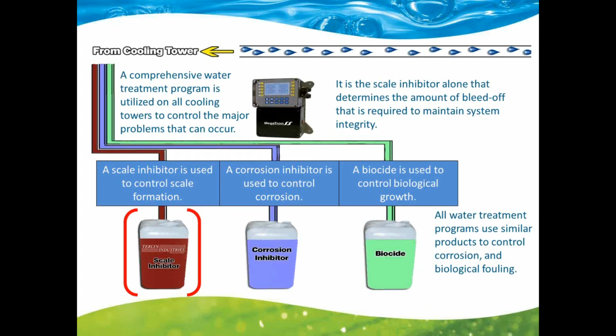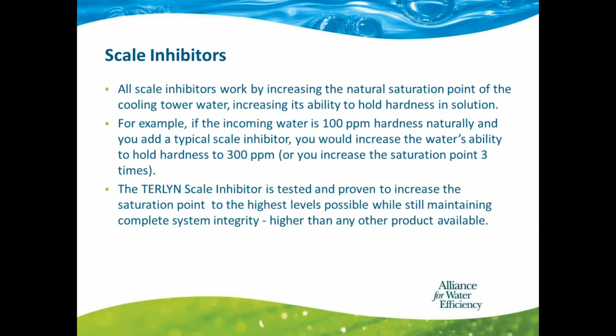It's the scale inhibitor that allows for water conservation in a cooling tower. Next slide, please. So, all scale inhibitors work by increasing the natural saturation point of cooling tower water, increasing its ability to hold hardness in solution. So, for example, if the incoming water is 100 parts per million hardness naturally, and you add a typical scale inhibitor, you would increase the water's ability to hold hardness to 300 parts per million, or you increase the saturation point 3 times. The TERLYN scaling inhibitor is tested and proven to increase the saturation point to the highest levels possible while still maintaining complete system integrity, higher than any other product available.